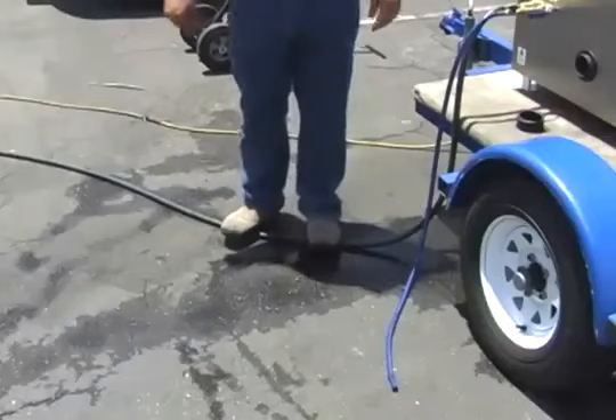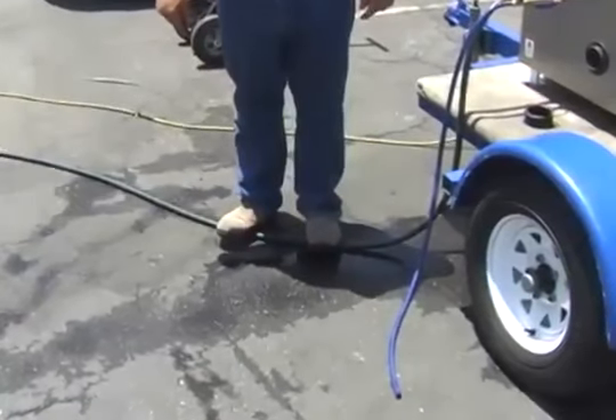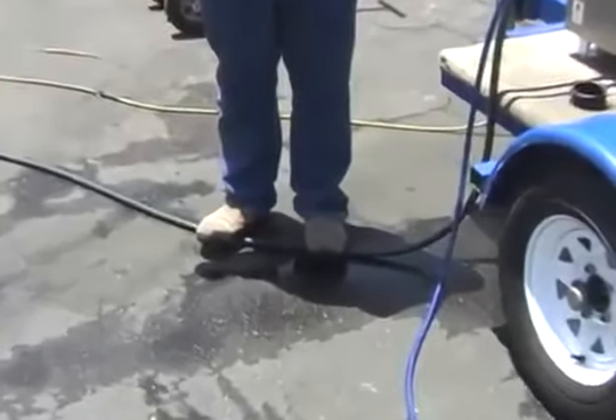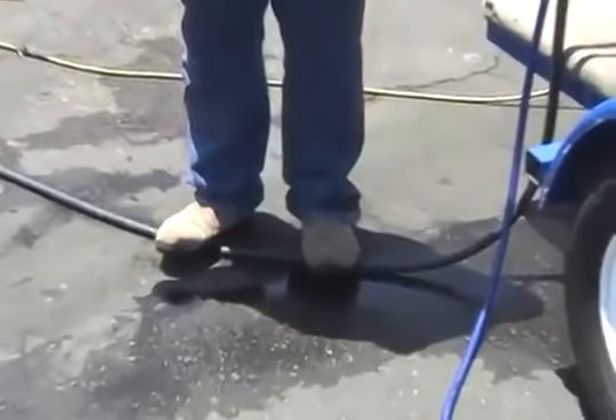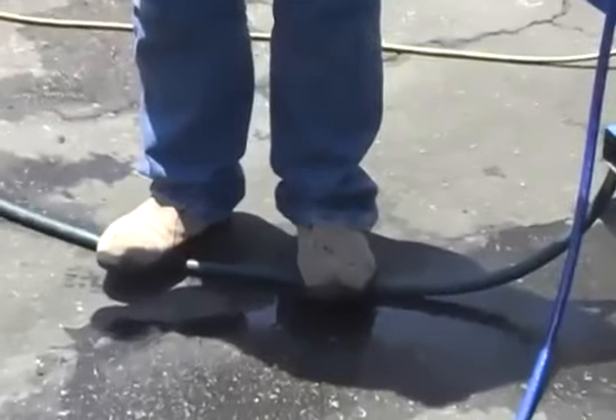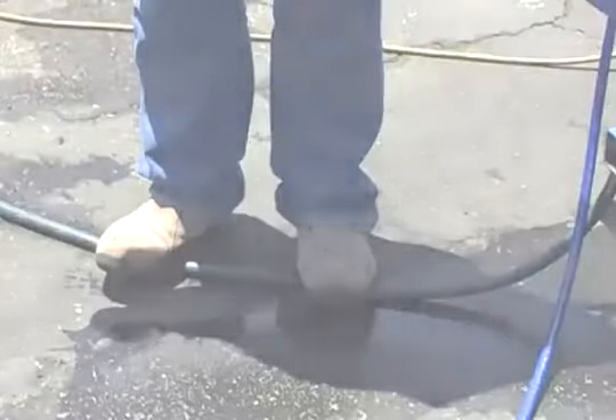One way to test this is to stand on the hose and feel the water pressure under your feet. If the hose remains stiff, then pressure is being well maintained. If the hose collapses, then begin troubleshooting the water supply as it may have been turned off, does not have service, or is damaged.